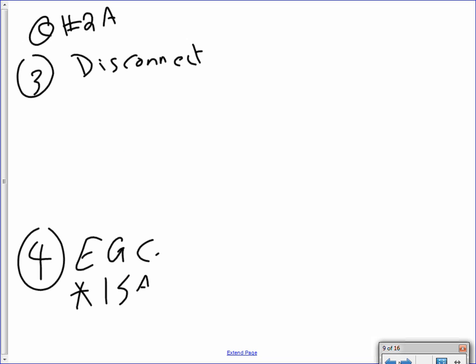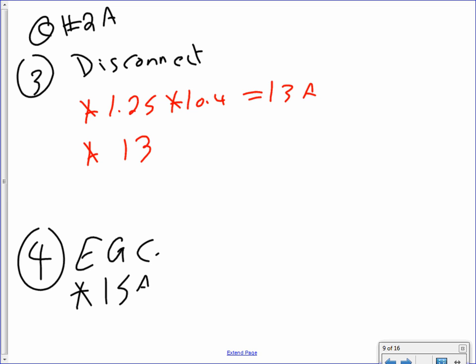Next, disconnect. For my disconnect, guys, I'm going to use 1.25 multiplied by 10.4. I came up with 13 amps. Okay, now, here's what you do with the 13 amps though. Here's what you can size. You have a couple of options. Option number one, guys, is to go to 312. That will get you a 30 amp 2-pole disconnect.